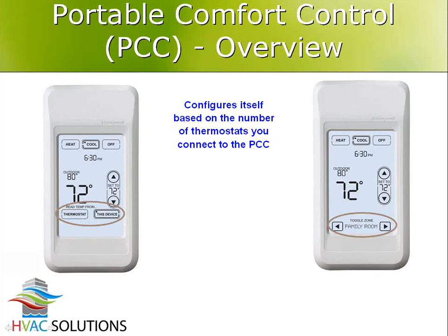The portable comfort control is a pretty slick device, and it can do lots of different things for different applications. It's a handheld device. It sits about 6 inches tall by 3 inches wide. It's about the size of a TV remote, if you will. Runs on batteries. And what this can be used to do is it can be used to interrogate your thermostats and override their set points. So if you're sitting on your couch, with this thing sitting next to the TV remote, and you're feeling hot or cold, you pick it up, press the button, say I want a colder set point, and it overrides your thermostat and tells it to do that.